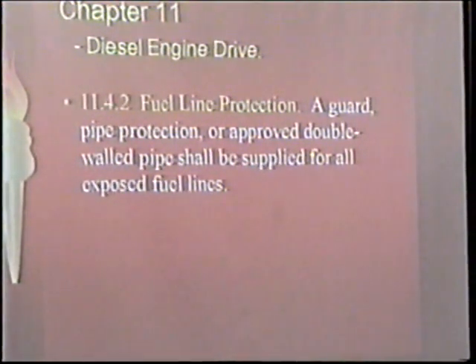This is new because now they're talking about a double-walled pipe for exposed fuel lines on diesel engines. Out of all the diesels I've seen, I bet since we did the mail garage, I don't think I've seen a guard around a diesel fuel pump or fuel pipe, and it's always been in the spec. But now they're talking about you put a guard around them, or you can use the approved double-walled pipe.